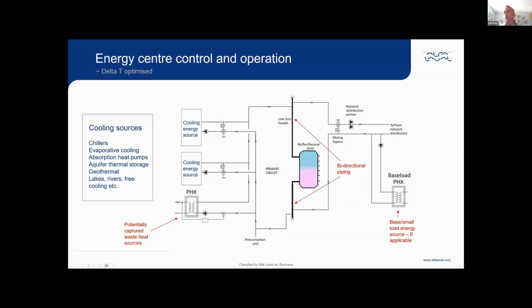And one of the ways I like to do that is with bidirectional piping on the thermal store, so that the thermal store is connected with just 2 pipes and not 4, which is more traditional. The problem with having a 4-pipe connection is you get mixing in that thermal store and you lose your stratification, you lose your delta T. With a 2-pipe arrangement, we will have a delta on the store that is the same as on the network, and that will create a small stratification layer between the hot and the cool, or the warm and the cool, depending on the system.